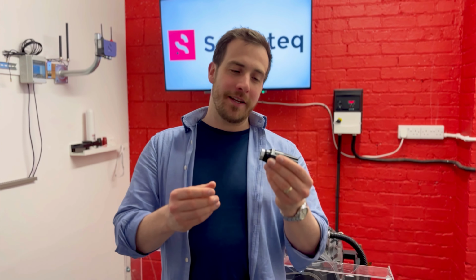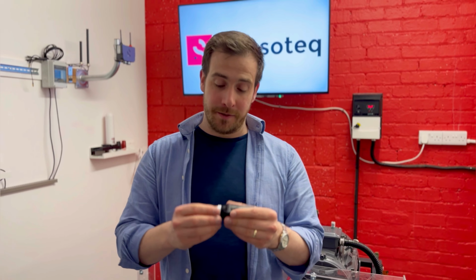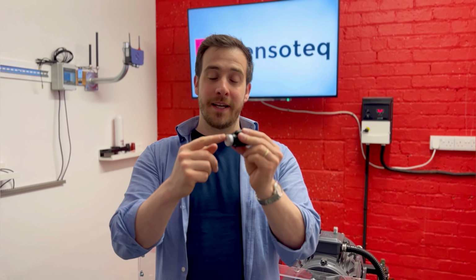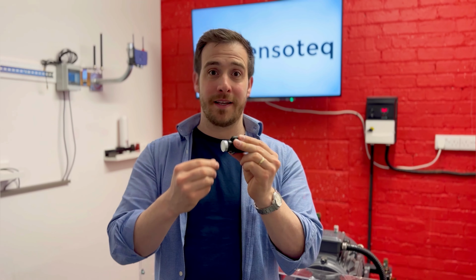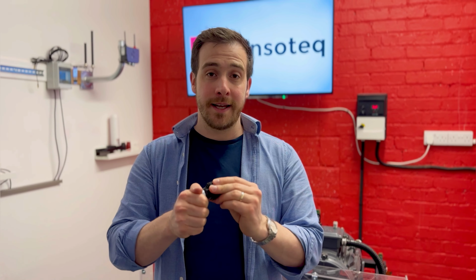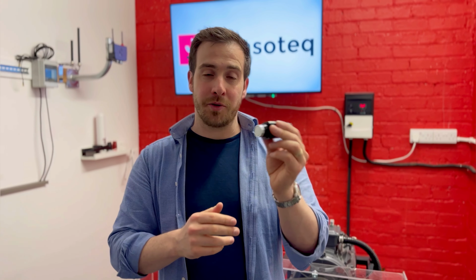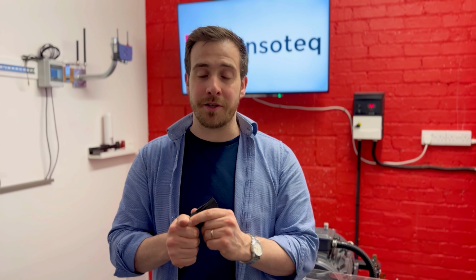There's a lot that needs to be taken into consideration when designing a wireless vibration sensor to get the most out of the data that comes from your machine. One of the most important considerations is related to the footprint of the sensor, and that is really denoted as the size of the base that connects to your machine. This could be a magnet, like is shown here, or it could be a stud mount, or it could be another mounting method as per the installation requirements of your sensor.